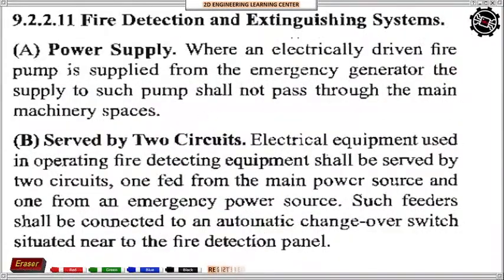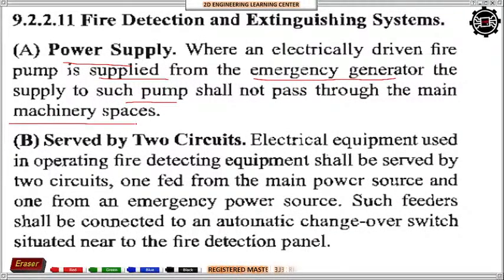Okay, so fire detection and extinguishing systems. So for power supply, when an electrically driven fire pump is supplied from the emergency generator, the supply to such pump shall not pass through the main machinery spaces. So that is to avoid na masira yung ating supply line, no?